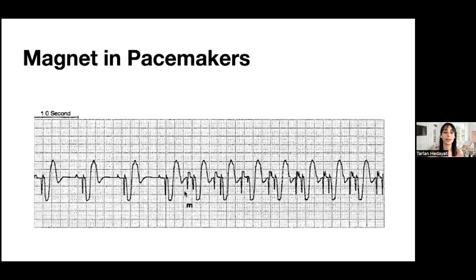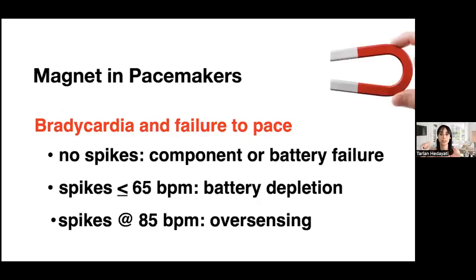When they put that magnet on, the atrial pacemaker wasn't working before because it didn't need to work—the patient was making their own P waves. But when you put the magnet on, you tell the pacemaker to stop sensing, stop running surveillance, stop looking for stuff, and just start pacing. So now you've fired up that atrial pacemaker, ventricular pacemaker, atrial, ventricular, everything firing the way it would if it needed to all the time. That's what a magnet does to a pacemaker.